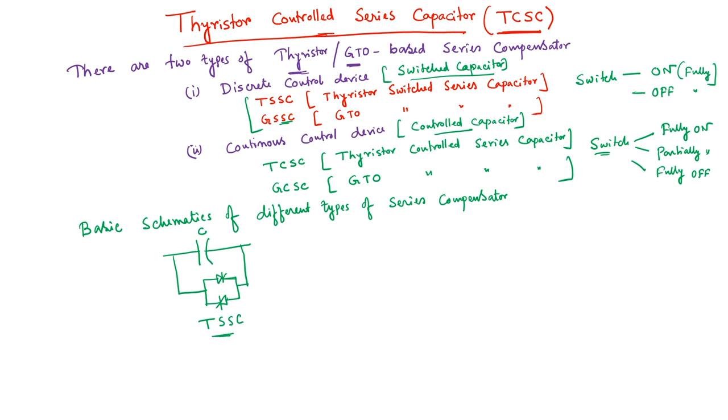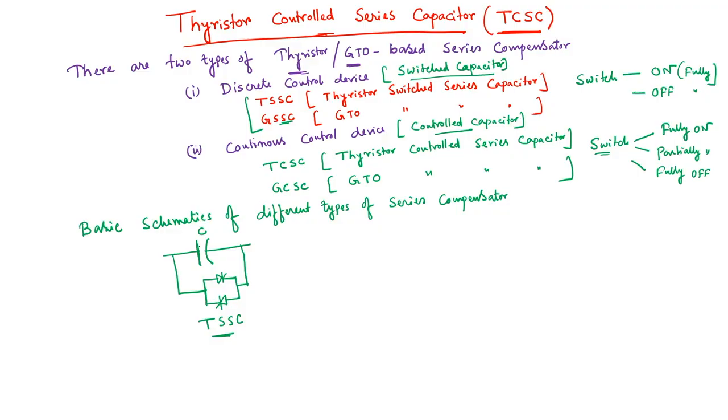Here you can see if both the switches are on, then it will create a short circuit path and it will bring out the capacitor from the system, okay. And when they are fully off, the capacitor will be in the system and it will act as a fixed capacitor. When both the switches are turned on, it will act as a bypass capacitor, or it will act as a short circuit. Okay.